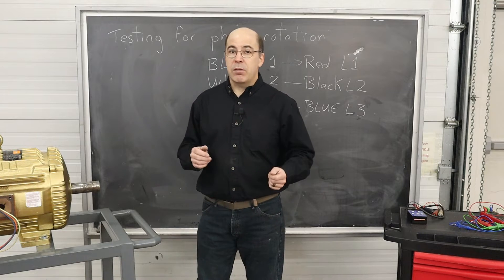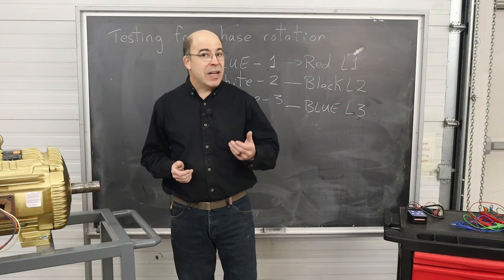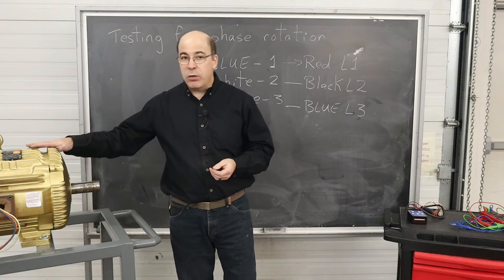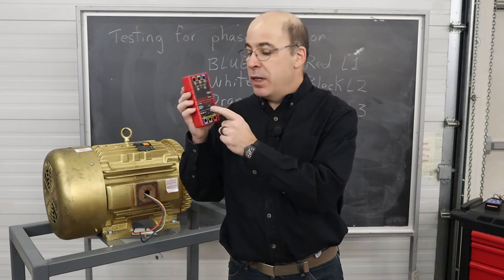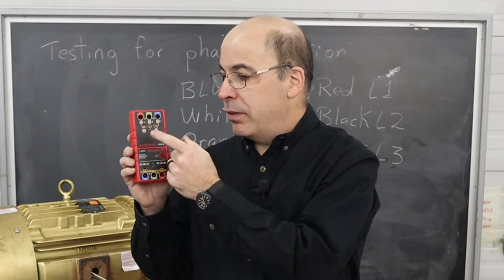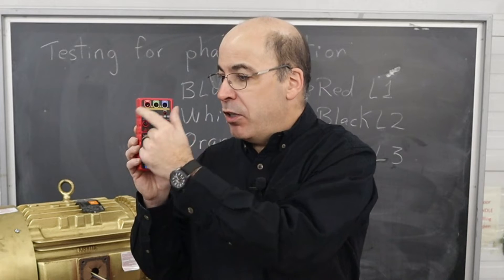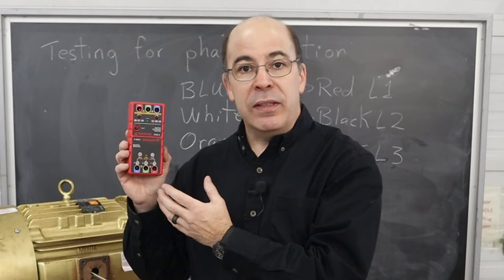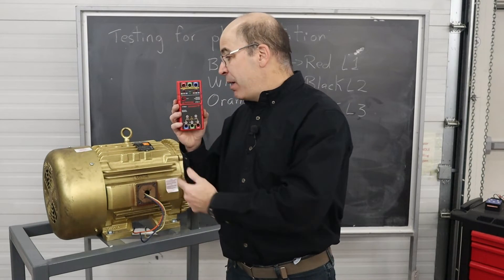I'm going to bring the motor closer and grab a phase rotation meter that will allow me to check this. The nice thing about the unit I'm using is I don't need electricity or to hook up the motor to do this assessment. The device is produced by a company called Amprobe. I particularly like it because it gives me the ability to take measurements on a live panel to determine phase rotation, and I can also use it to test motors that are not powered to determine their direction of rotation.